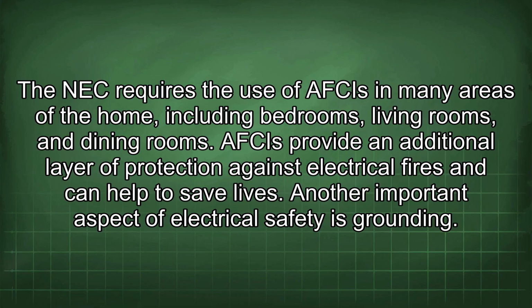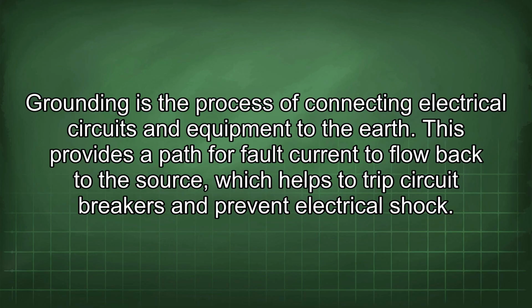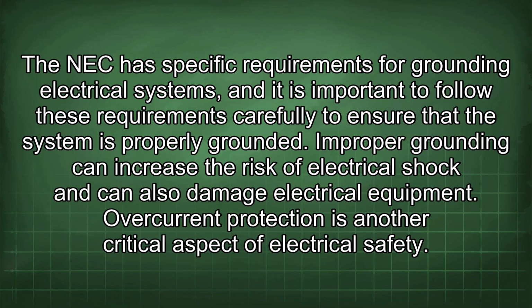Another important aspect of electrical safety is grounding. Grounding is the process of connecting electrical circuits and equipment to the earth. This provides a path for fault current to flow back to the source, which helps to trip circuit breakers and prevent electrical shock. The NEC has specific requirements for grounding electrical systems, and it is important to follow these requirements carefully to ensure that the system is properly grounded. Improper grounding can increase the risk of electrical shock and can also damage electrical equipment.